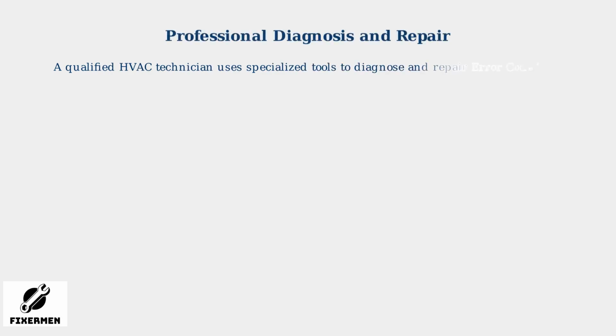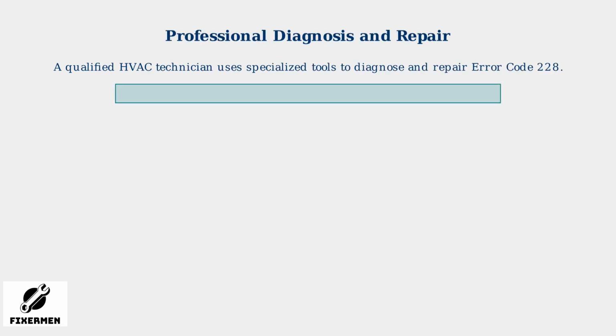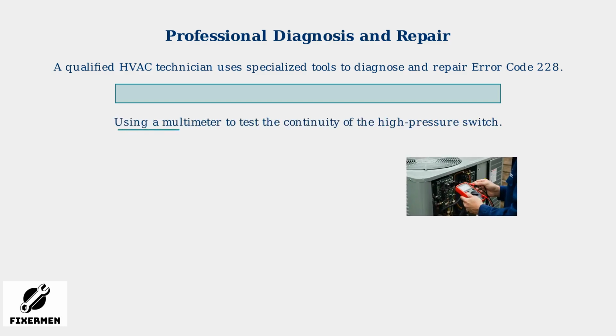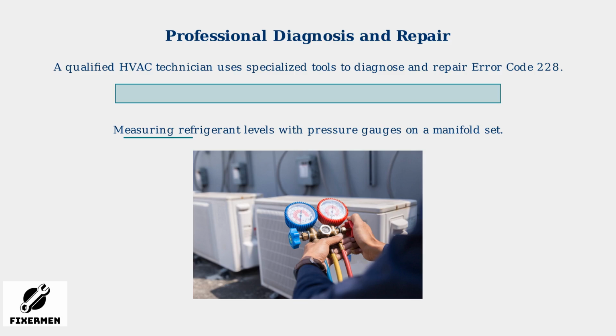When error code 228 appears, a qualified HVAC technician begins the diagnosis process. They use specialized tools to identify the root cause safely and accurately. The technician starts by using a multimeter to test the electrical continuity of the high-pressure switch. This verifies if the switch is opening and closing properly at the correct pressure thresholds. Next, the technician connects pressure gauges to measure the refrigerant pressure levels in the system. This helps determine if the refrigerant charge is correct or if there's an overcharge causing the high pressure.